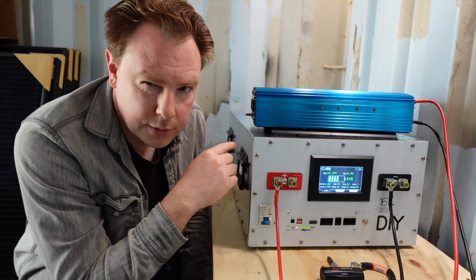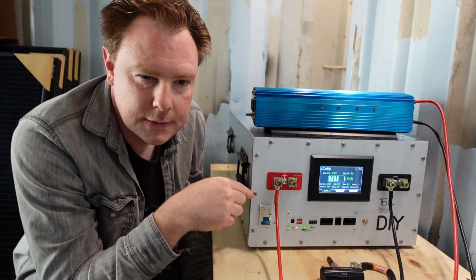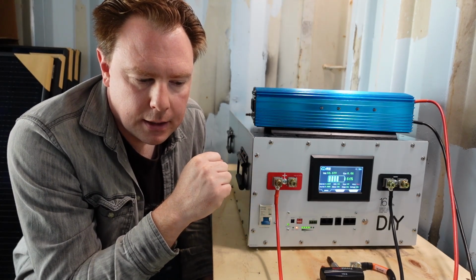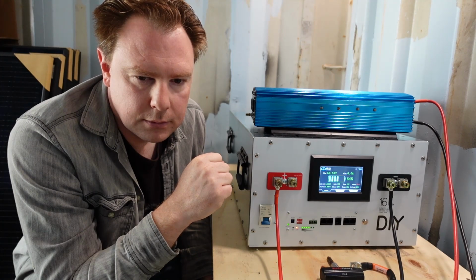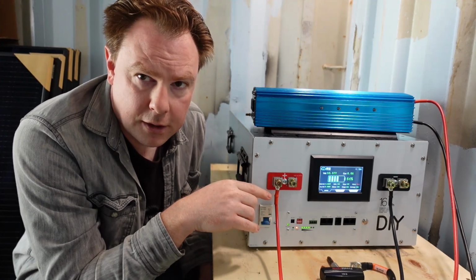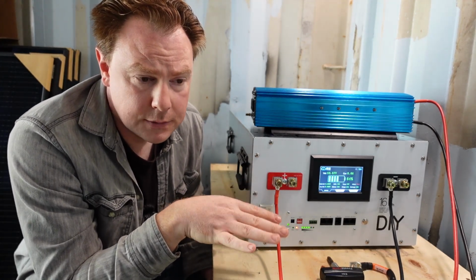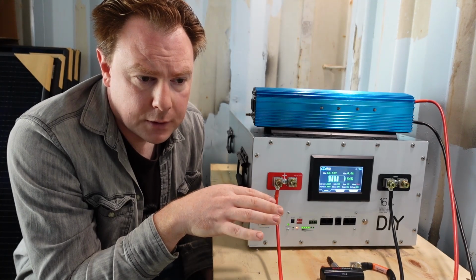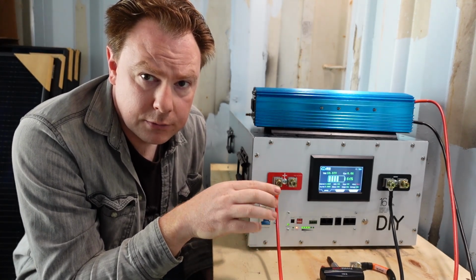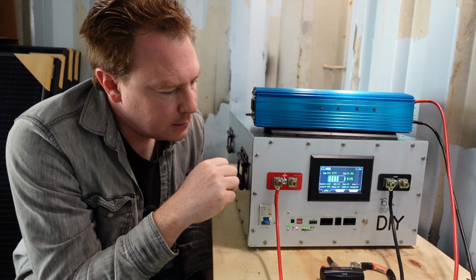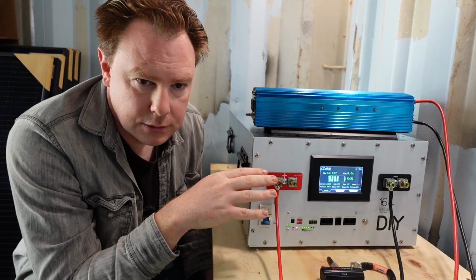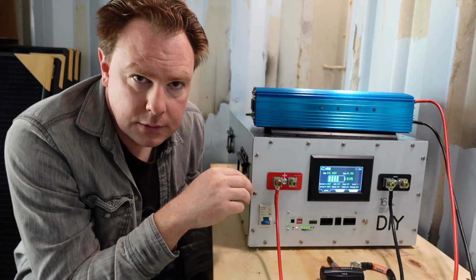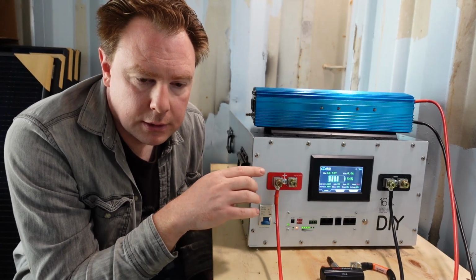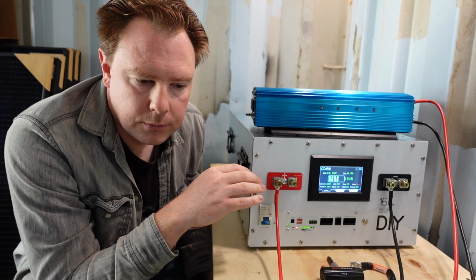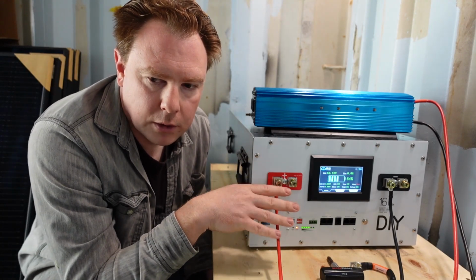So I try to keep all my bus bars and connections the same type of metal. I'm going back and forth between copper and aluminum all throughout this, and I don't particularly like that. Copper is great. Aluminum can be fine, but you have to remember that aluminum oxidizes, and you can get an oxide layer build up on those bus bars that can make for bad or weird connections. So you just have to be a little more careful with your connections when using aluminum.